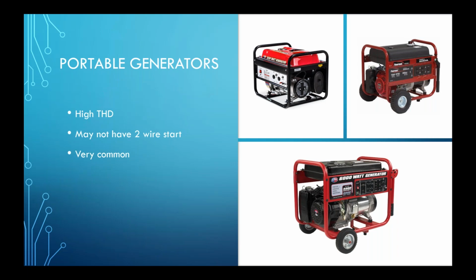So bringing that all full circle to the generators, we can handle the little generators. If they're these little portable guys, you're going to want to get a 2-wire start kit. The way that the Sol-Ark will talk to these generators and start them is a 2-wire start kit. These little guys typically don't have 2-wire start built into them. So there is a commercially available kit. You can get it at Grainger, Harbor Freight, whatever, all kinds of places. It's called a 2-wire start kit. So that's how we're going to talk to these little guys.